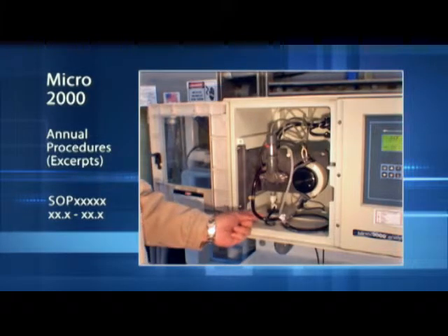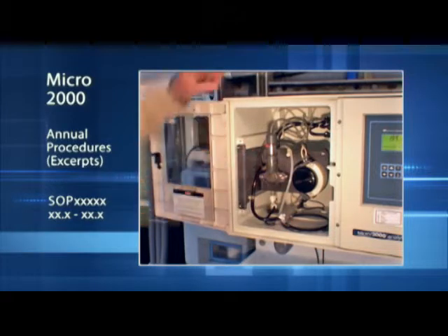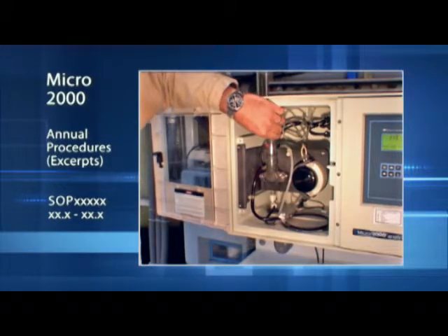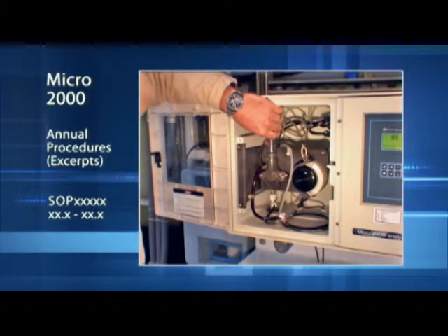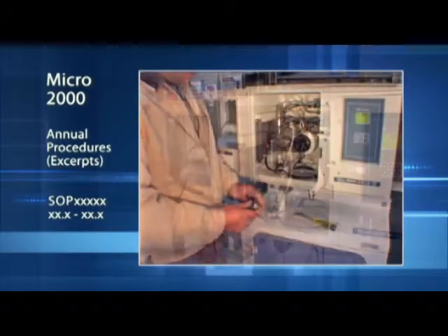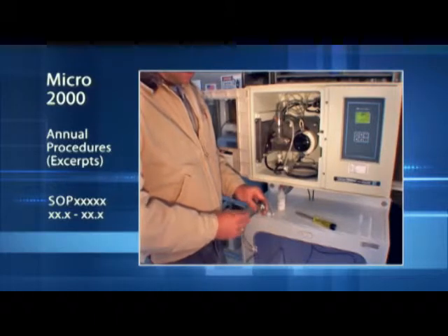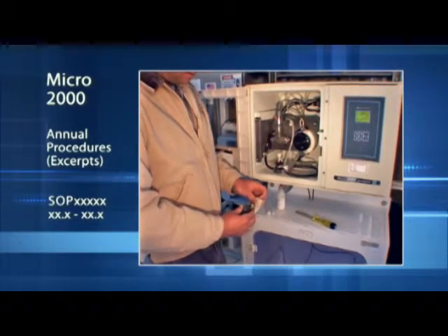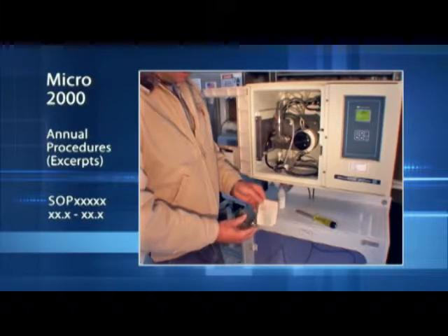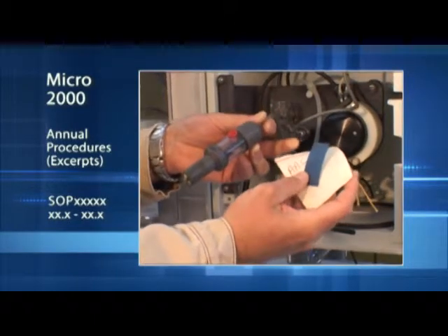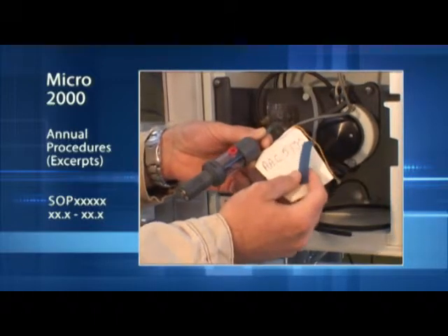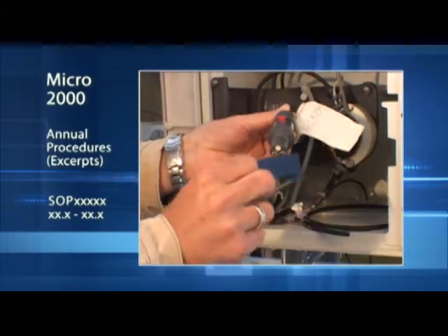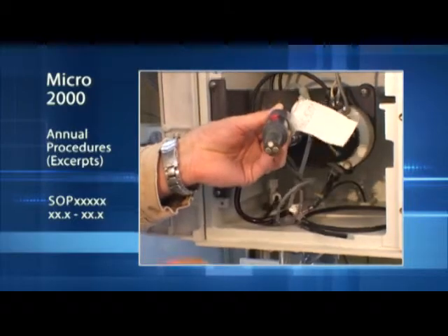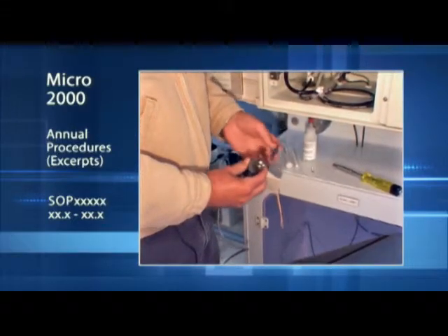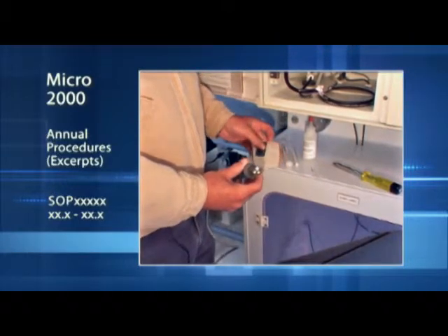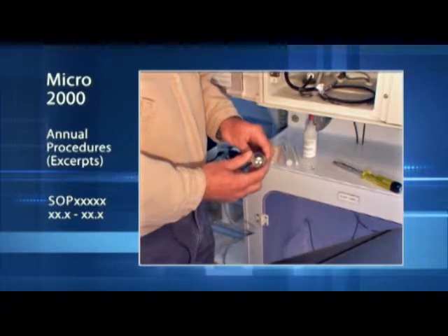Once you've replaced all the tubing inside the instrument, you can next perform a service on the probe. The probe can be removed simply by pulling it straight out. The first step is to wipe clean the analyzer tip to make sure that all the debris is removed. Using the blue cloth that comes with the instrument and is in the maintenance kit, simply wipe the titanium tips twice, very cautiously, to wipe any buildup that may be on them.